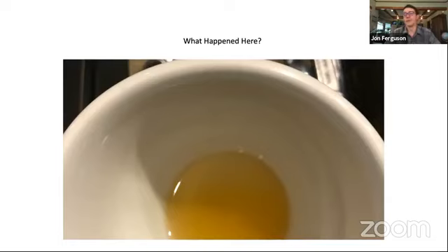So I switched it out and noticed that with the steam coming out of the wands, it was a little wet. The fill valve was completely full, the steam tank was completely full. I corrected that too, got it out, cleaned it up, and now it has a nice level.